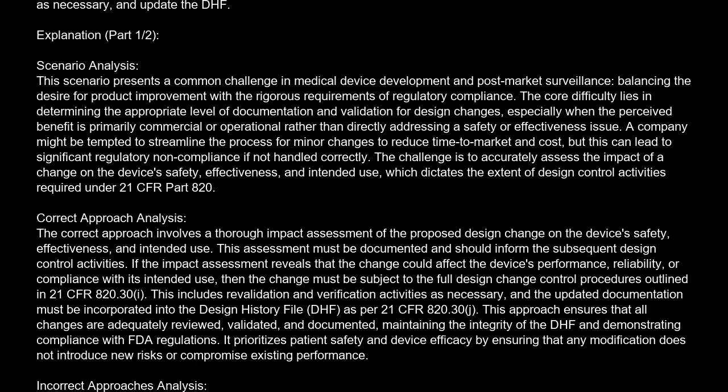30(I). This includes revalidation and verification activities as necessary, and the updated documentation must be incorporated into the design history file, DHF, as per 21 CFR 820.30(J). This approach ensures that all changes are adequately reviewed, validated, and documented, maintaining the integrity of the DHF and demonstrating compliance with FDA regulations.